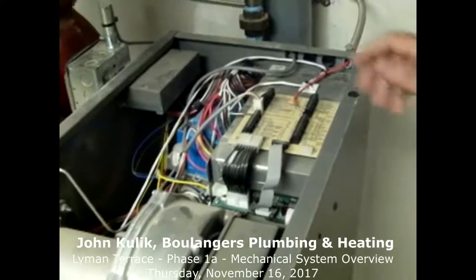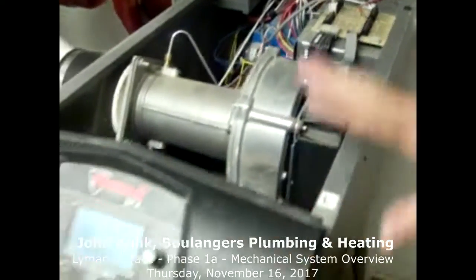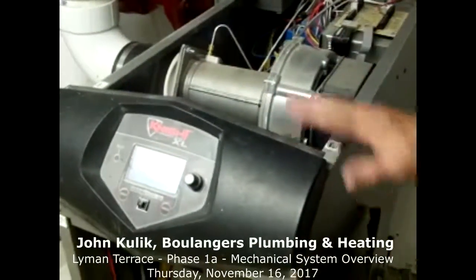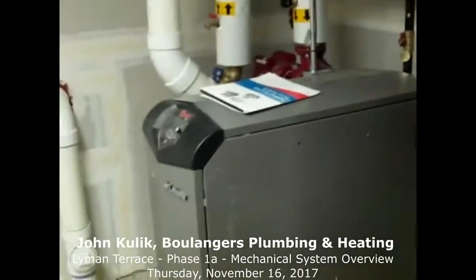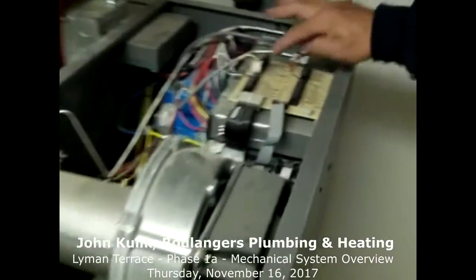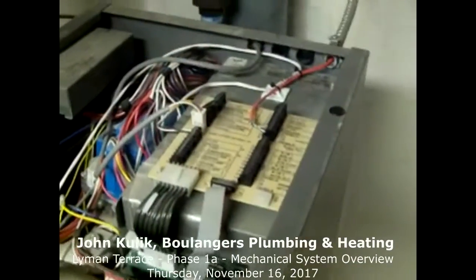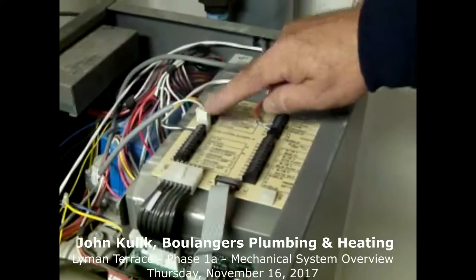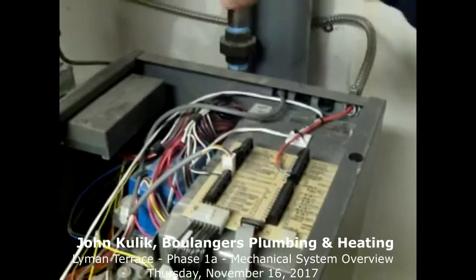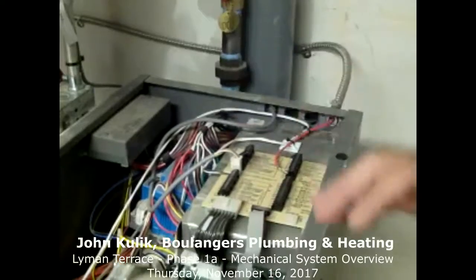Okay, this is the lag boiler in the cascade system, so it's boiler number 2. That's the lead. We can tell the only thing connected here on a wiring is the low water cutoff control, flow switch on the side, proving that if the pump fails, it will shut the boiler off.